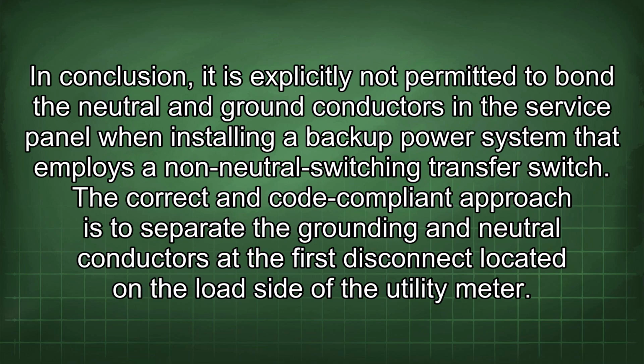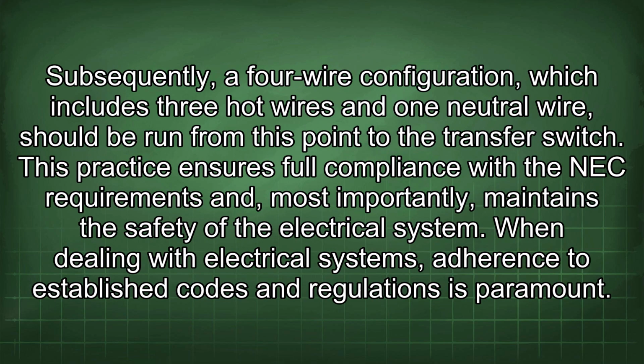In conclusion, it is explicitly not permitted to bond the neutral and ground conductors in the service panel when installing a backup power system that employs a non-neutral-switching transfer switch. The correct and code-compliant approach is to separate the grounding and neutral conductors at the first disconnect located on the load side of the utility meter. Subsequently, a 4-wire configuration, which includes 3 hot wires and 1 neutral wire, should be run from this point to the transfer switch.